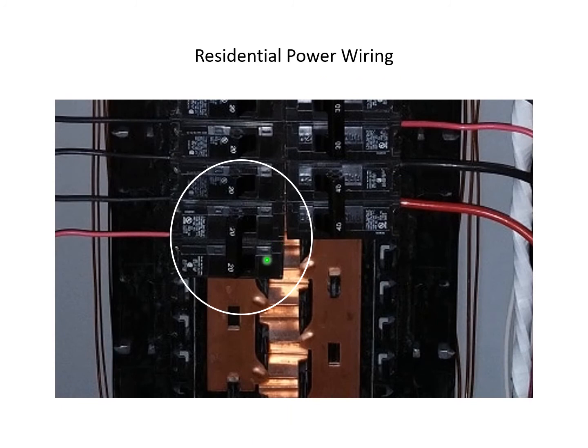But you can see that this breaker is actually two breakers mounted side by side. So one is fed from this side, and the other one is fed from this side. So you get 240 volts across here, and they're mechanically ganged together. You can see that's one bar, so that if one breaker or the other trips, either manually or due to overcurrent, they both will open up.